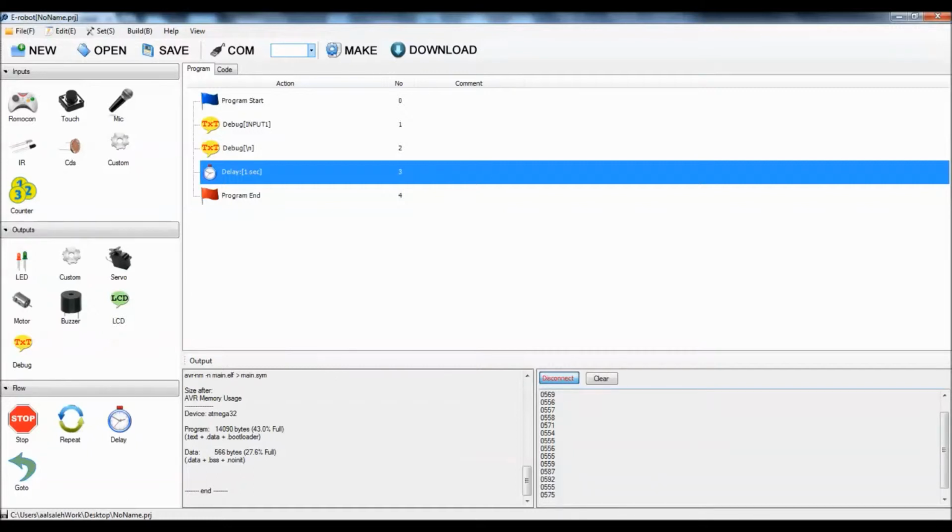And let me change the value for you. I'm gonna put a white paper on top of the IR sensor. Okay, now it's full. This is even further. I'm gonna get it closer. See how the value changes. And this is how to read an input using the debug screen. You read the value of the input.